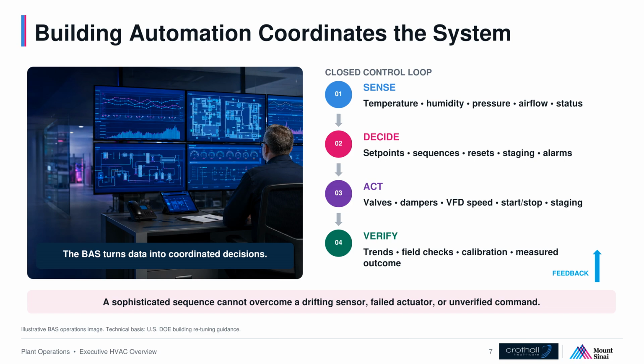Think of the building automation system as a loop, not a remote control. First, sense temperature, humidity, pressure, airflow, equipment status. Second, decide, compare set points, apply sequences, resets, staging, and alarms. Third, act, move valves and dampers, change variable frequency drive speed, start equipment, or stage capacity. Fourth, and this is the step people skip, verify. Trend the result, calibrate the sensor, and check the field condition. A command does not prove the actuator moved, and an actuator position does not prove the room responded.